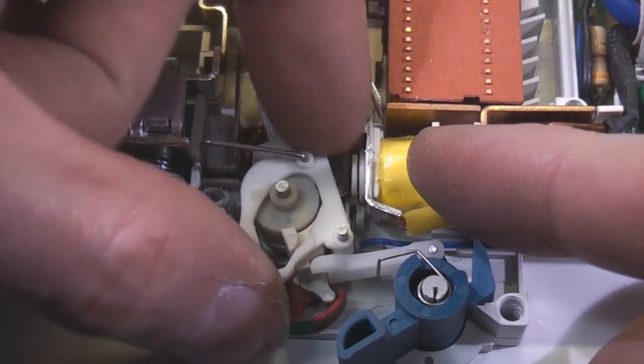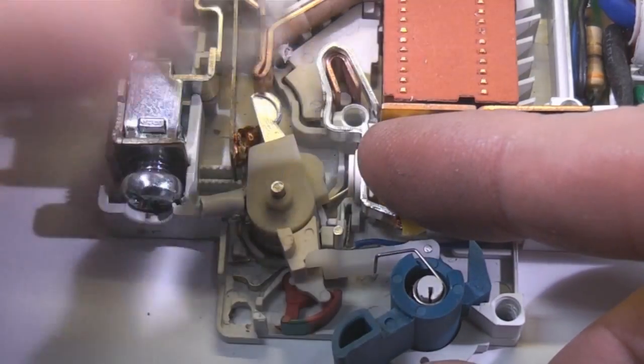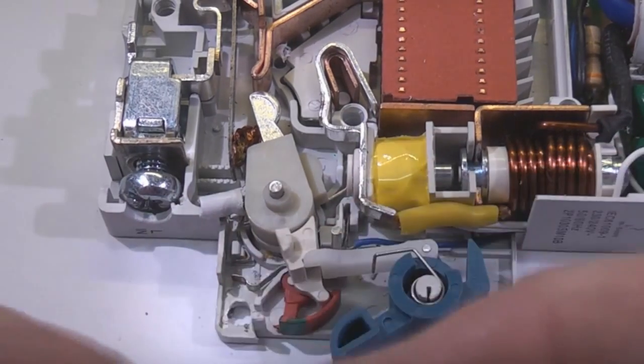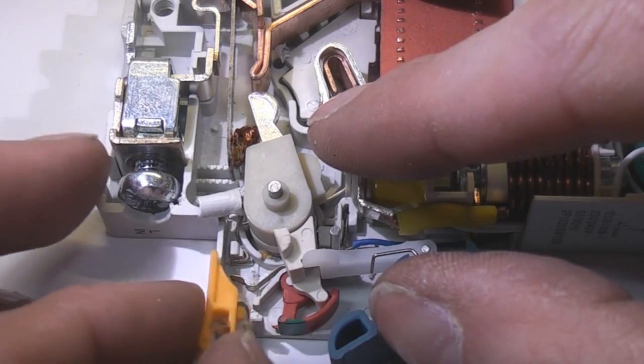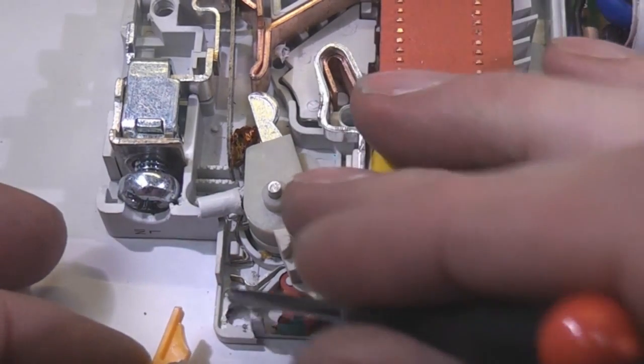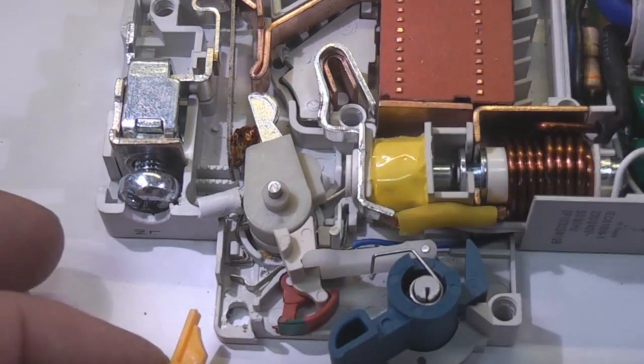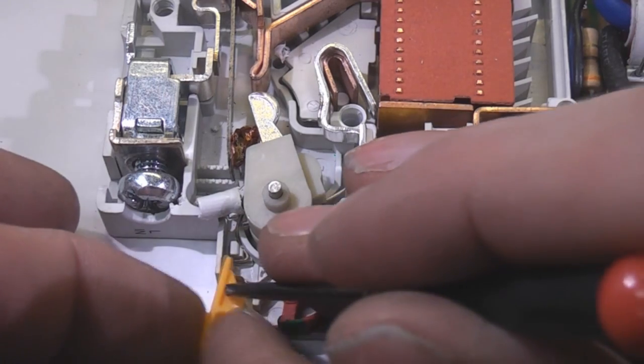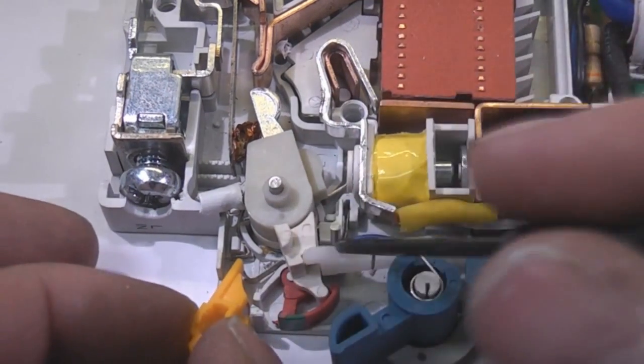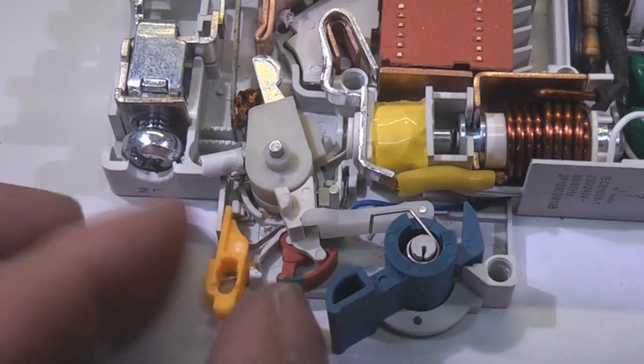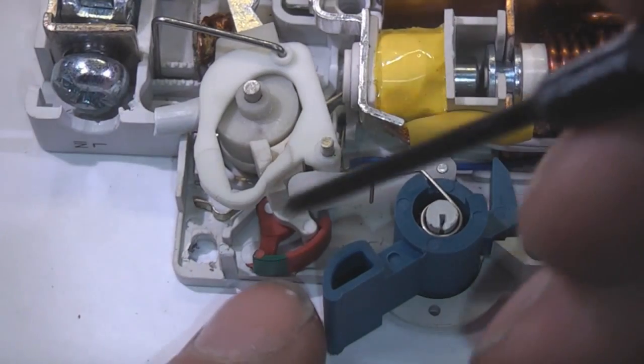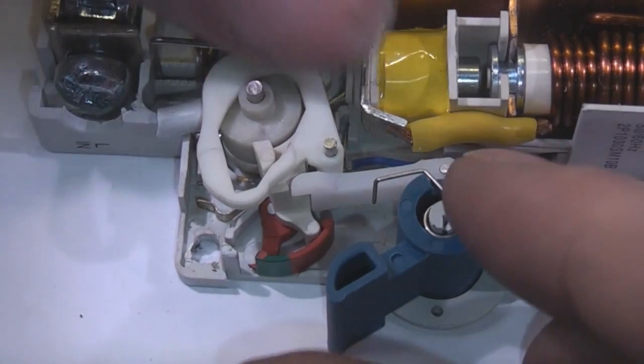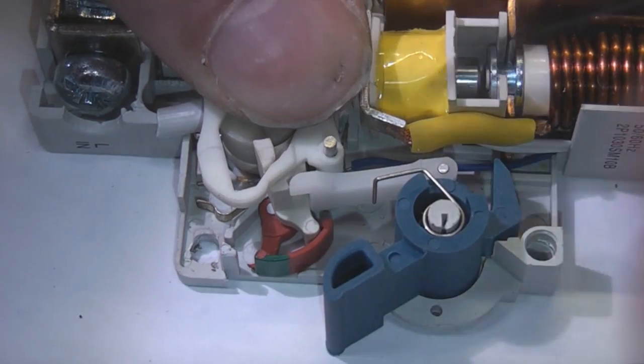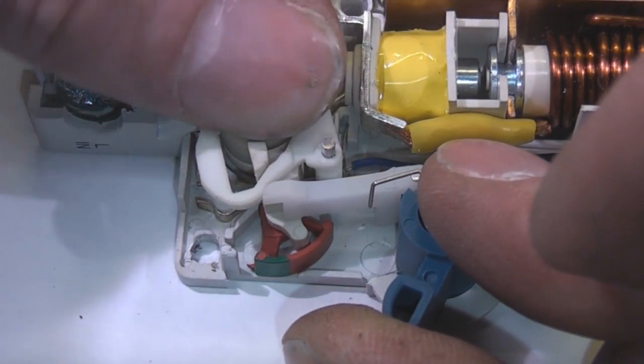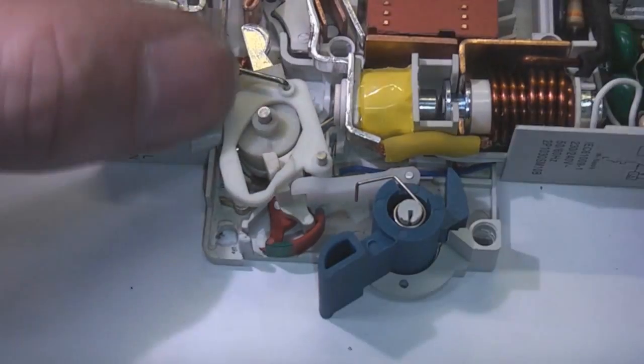And just underneath here you can see the contact that the test button uses. So the test button just fits in there and pushes down this contact to provide that bypass current flow around the transformer to trip it. So that's not actually part of this mechanism, it's just located here because it's mechanically convenient. Obviously it's only this top bit that goes through the front panel of the switchboard, so this button needs to be accessible. Interesting little detail how this front panel indicator works. You can see it's got this big hole in it, so it only changes state once the contact is fully engaged.